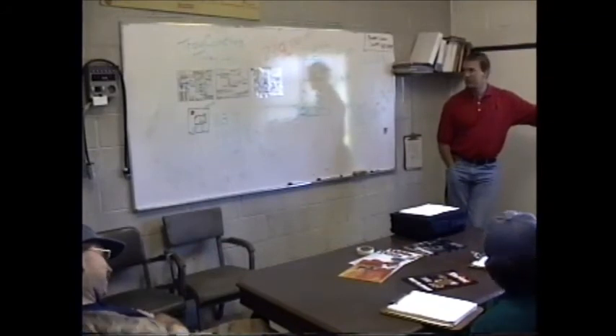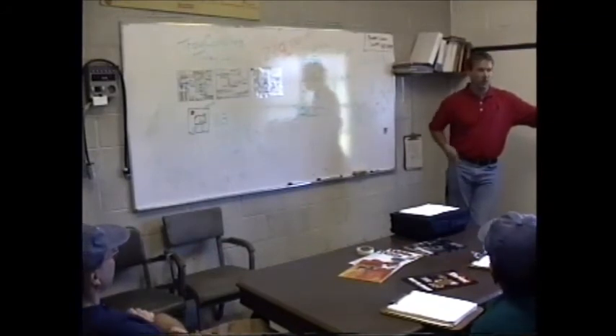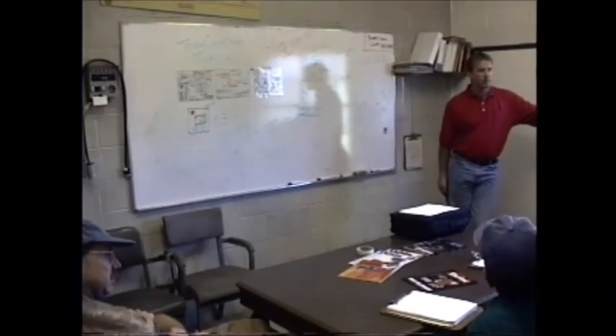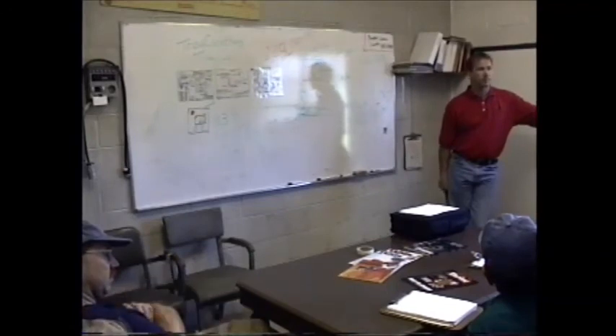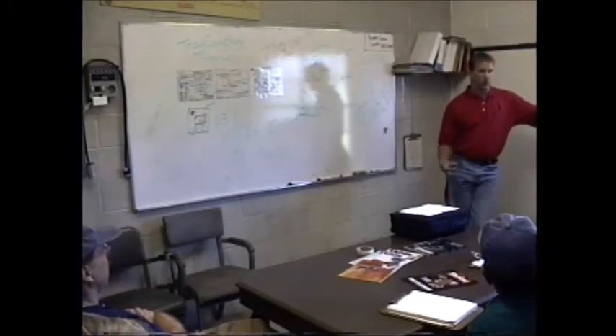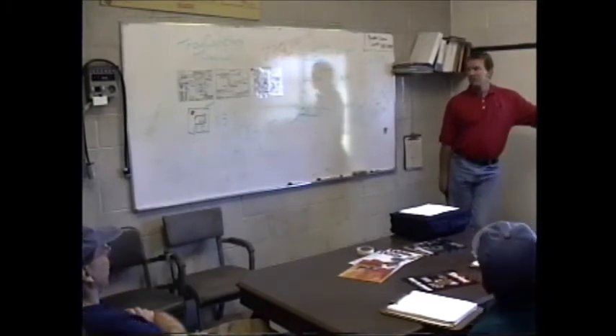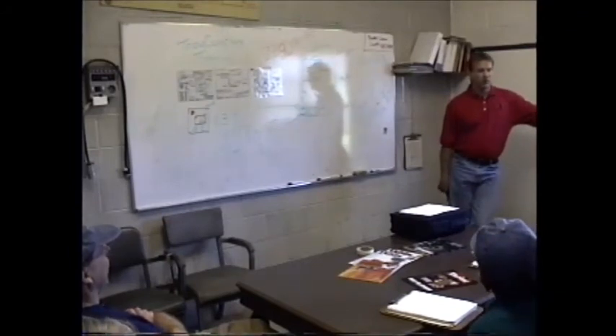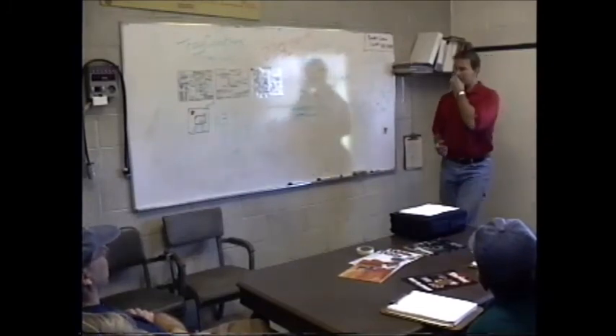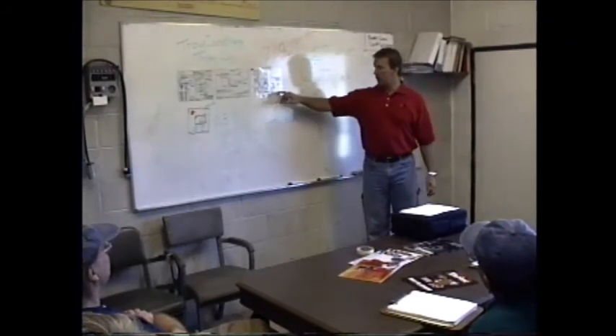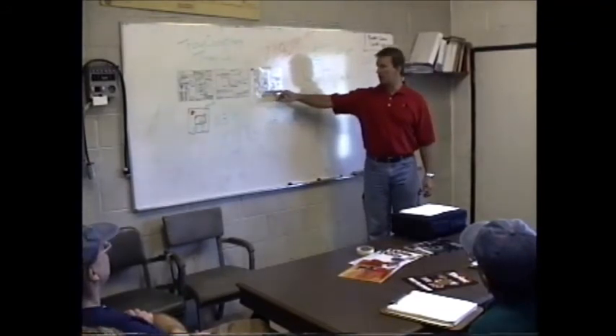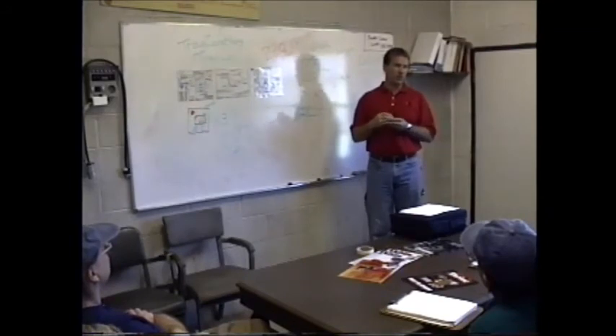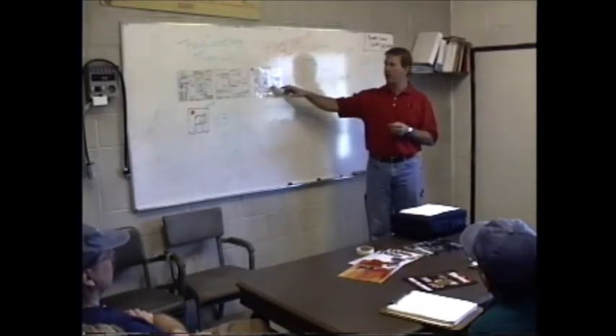Any other questions? Operation, maintenance, the whole thing. If we're drafting from a pond or one of the lakes up here or something like that, is there any abrasion consideration? You mentioned the mixing chamber with all the vanes. Is there any abrasion factor involved in it? You mean from the stuff that's in the water itself? Yeah, pebbles, grit. Shouldn't cause too much of a problem. Anything that can get through our strainer. Are they stainless steel? Yeah, those are stainless steel discs and they're welded in. The strainer port that cleans the water going to the heat exchanger has small enough ports that it's going to filter out anything that could possibly plug the heat exchanger.